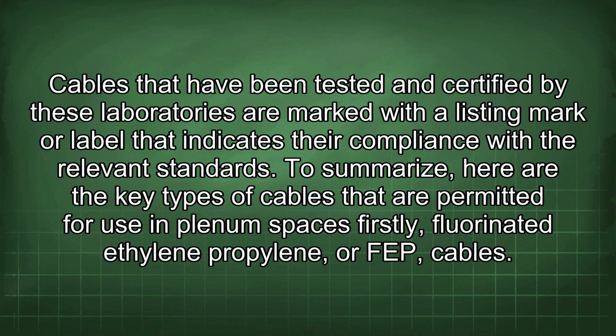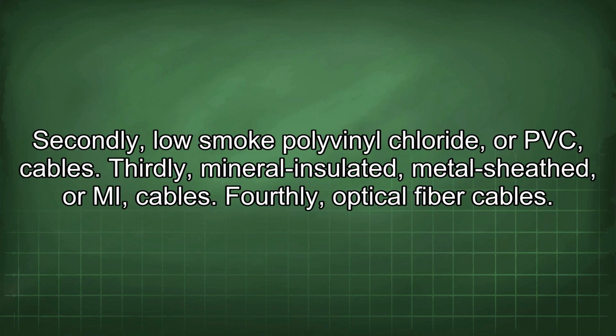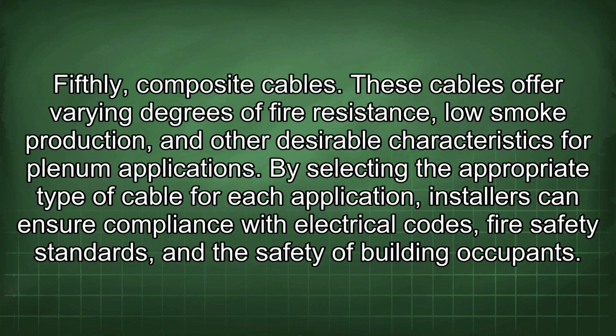To summarize, here are the key types of cables that are permitted for use in plenum spaces. Firstly, fluorinated ethylene propylene, or FEP cables. Secondly, low-smoke polyvinyl chloride, or PVC cables. Thirdly, mineral-insulated metal sheath, or MI cables. Fourthly, optical fiber cables. Fifthly, composite cables. These cables offer varying degrees of fire resistance, low smoke production, and other desirable characteristics for plenum applications. By selecting the appropriate type of cable for each application, installers can ensure compliance with electrical codes, fire safety standards, and the safety of building occupants.